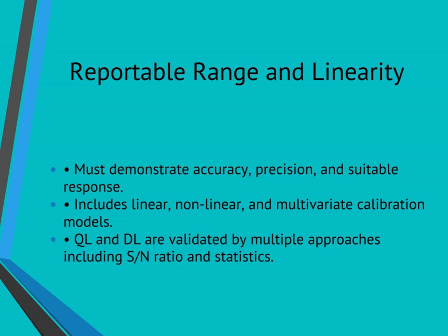Validation must demonstrate accuracy, precision, and response linearity or functional equivalence across this range. For detection and quantitation limits, methods include signal-to-noise ratio analysis, statistical derivation using slope and standard deviation, and visual estimation. The guideline provides flexibility for nonlinear responses, which are common in immunoassays and biological methods.